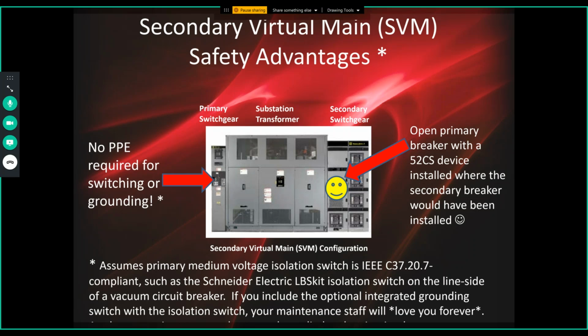And now you have a 3-position switch that's closed, open, and then grounded with visible confirmation of blade disconnect, both for phase blades and grounding through separate front arc-rated viewing windows. It is a wonderful device. And I'll tell you, as much as I've preached this device to people, and they kind of listen, after we've delivered this switch to customers, the maintenance people just fall in love with it.